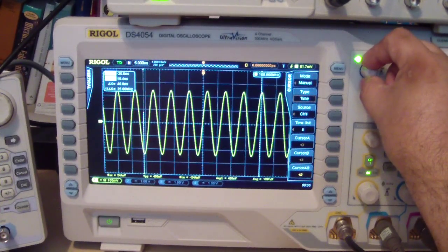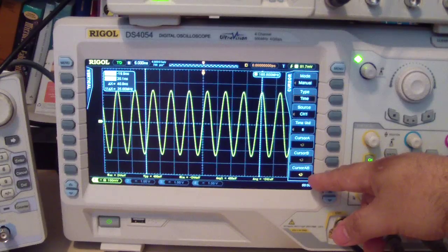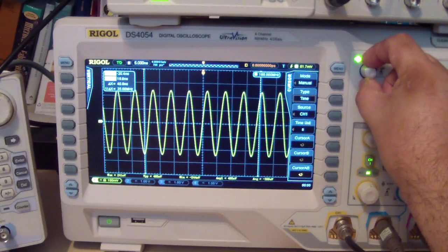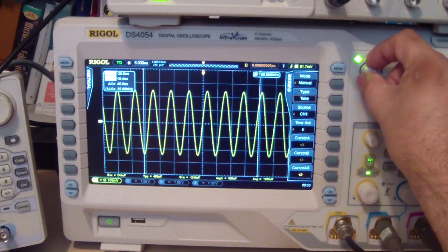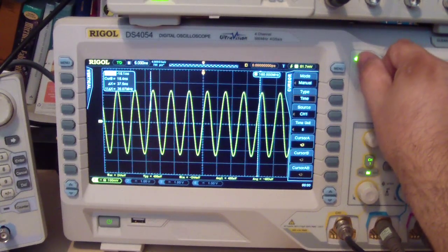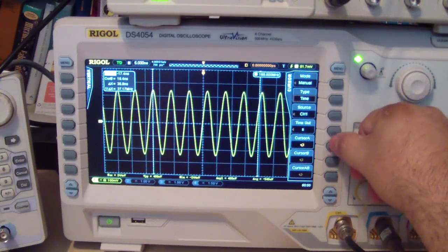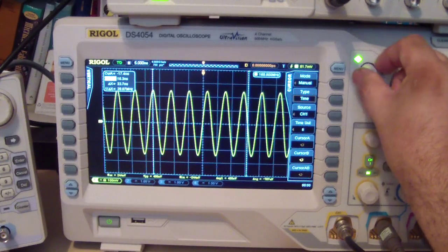So in the manual, you get the output of your cursors on the left side, and I'm not sure if you can see, but it has cursor A and B lit up. That means that if they both lit up, they move together. If you want to move cursor A, you can move cursor A alone by itself. Press B, moves cursor B.